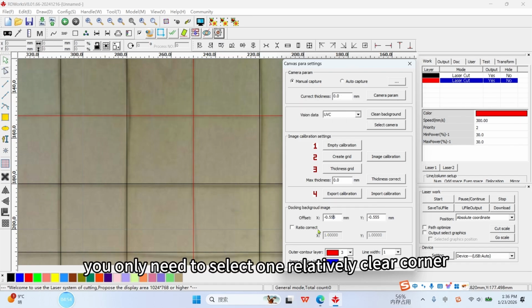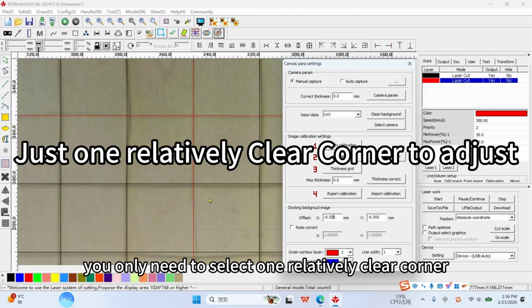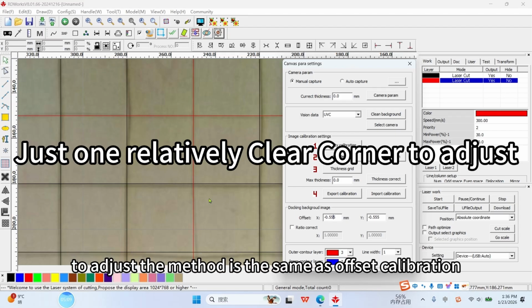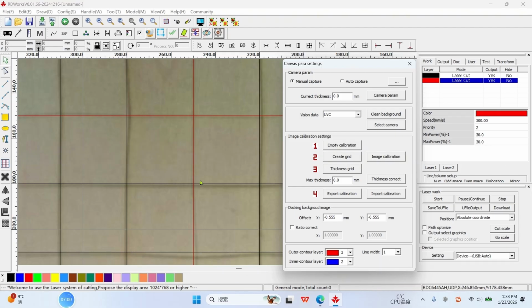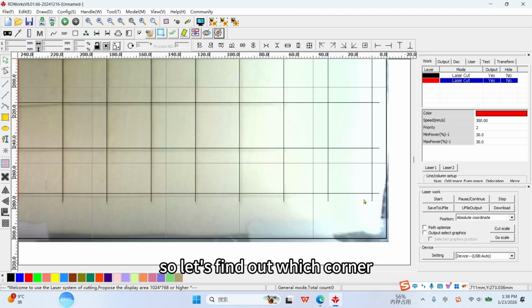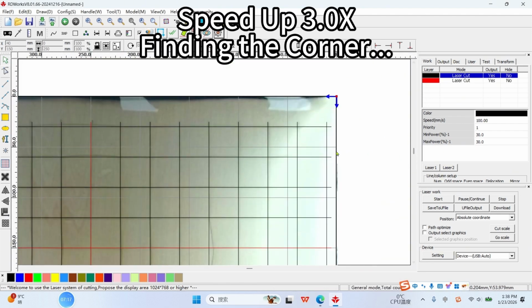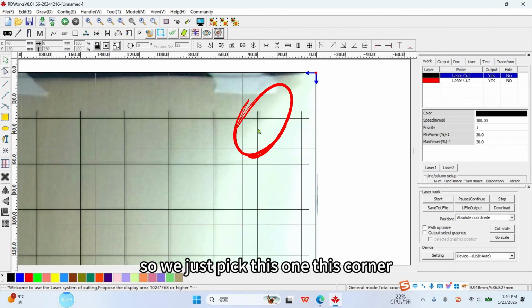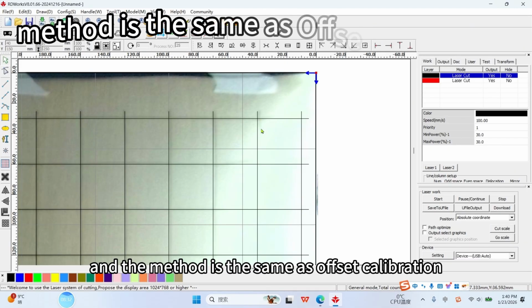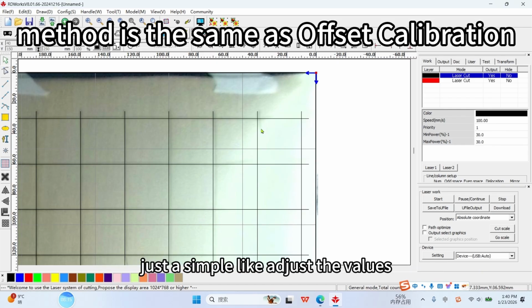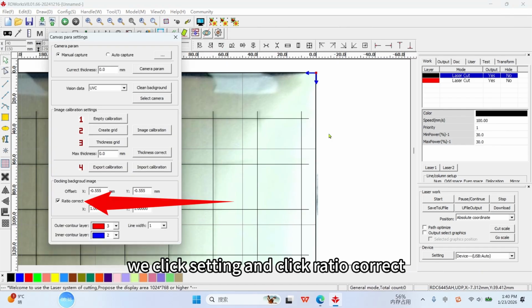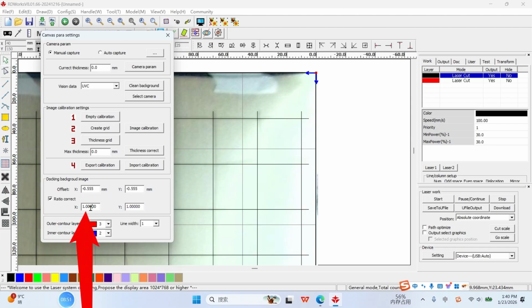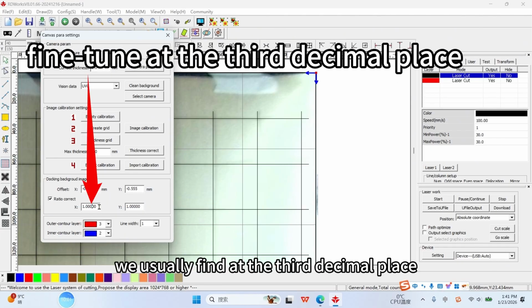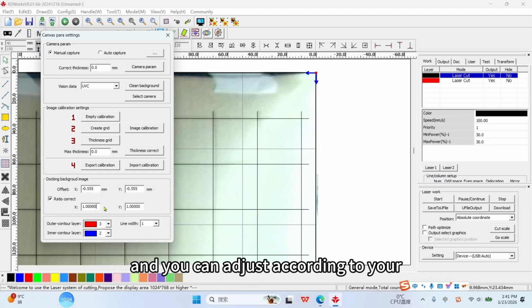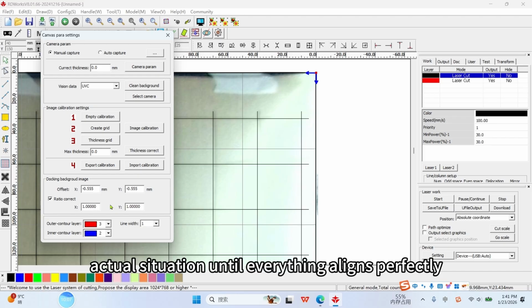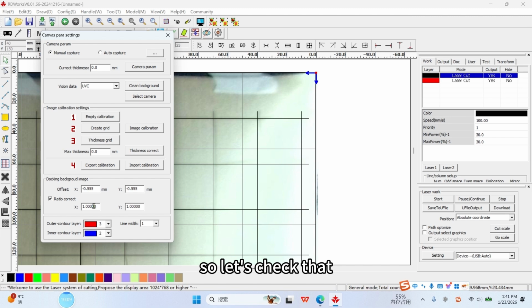For scale correction, you only need to select one relatively clear corner to adjust. The method is the same as offset calibration. So let's find out which corner. So we just pick this one, this corner. And the method is the same as offset calibration, just simply adjust the values. We click setting and click ratio correct. We usually fine-tune at the third decimal place, and you can adjust according to your actual situation until everything aligns perfectly. So let's check that.